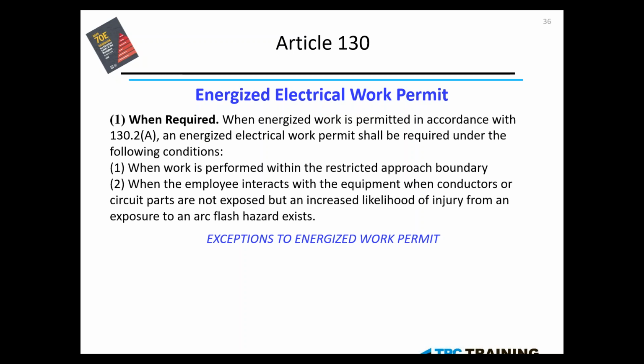Energized electrical work permit, when it is required. When energized work is permitted: 0 to 50 volts, troubleshooting, and when it creates a larger hazard. An energized electrical work permit shall be required under the following conditions: when work is performed within the restricted approach boundary, and number 2, when the employee interacts with the equipment when conductors or circuit parts are not exposed, but there is an increased likelihood of injury from an exposure to an arc flash hazard.